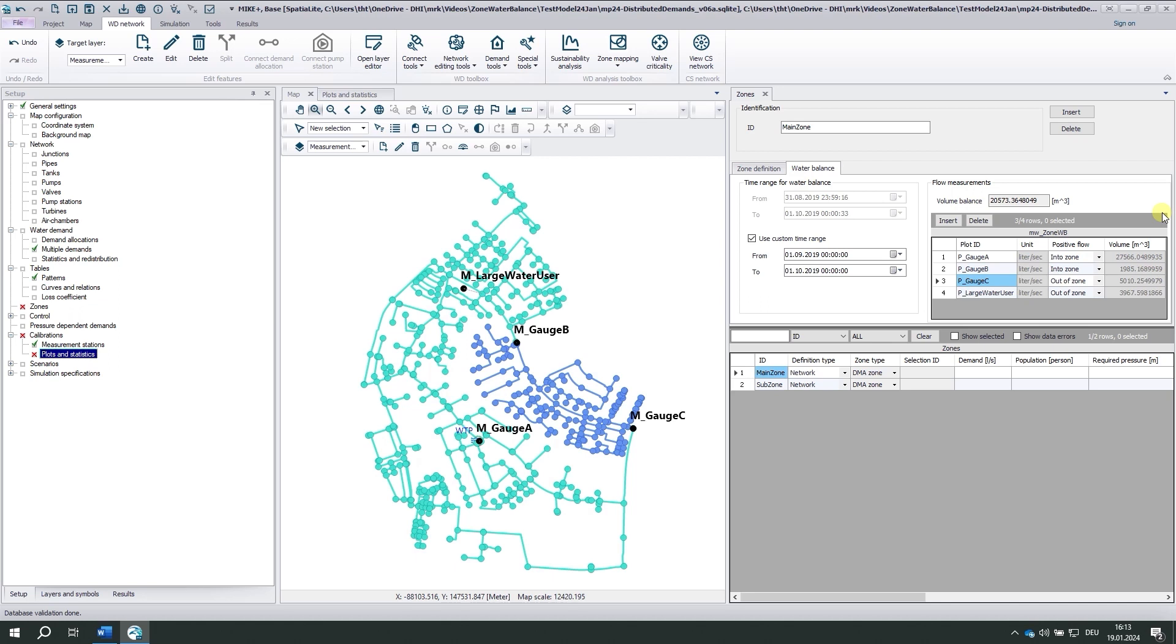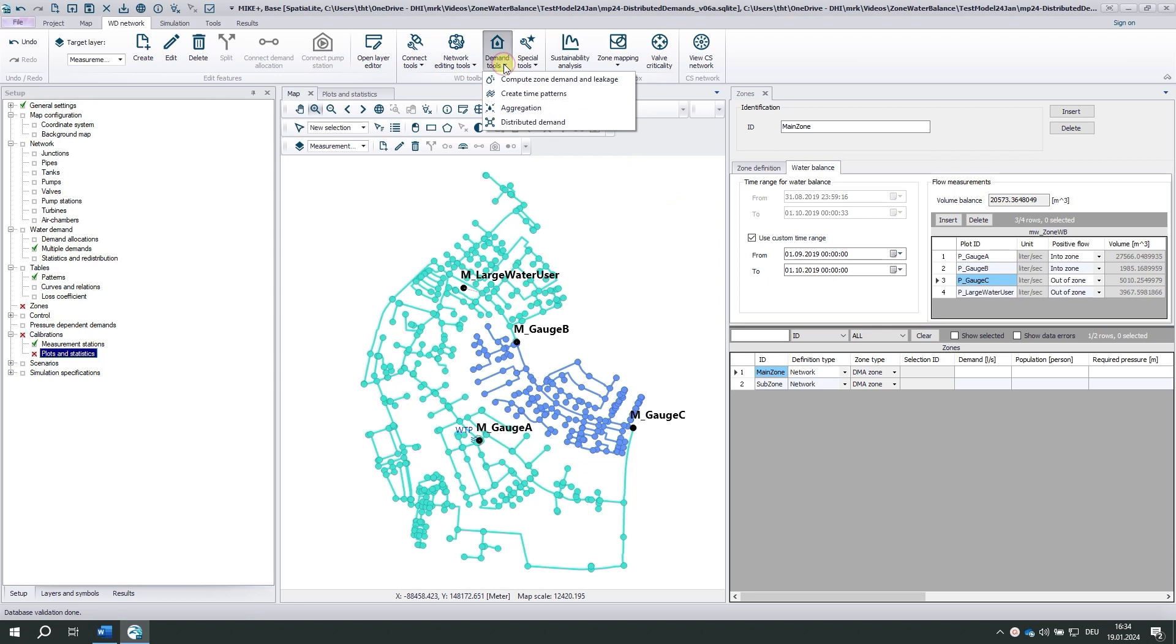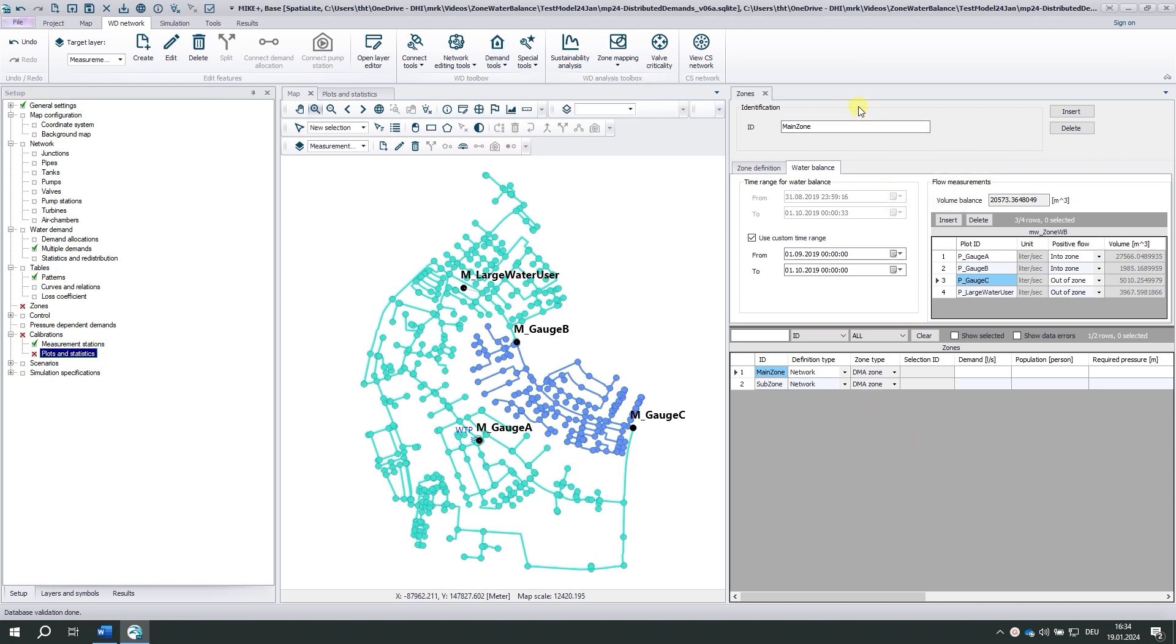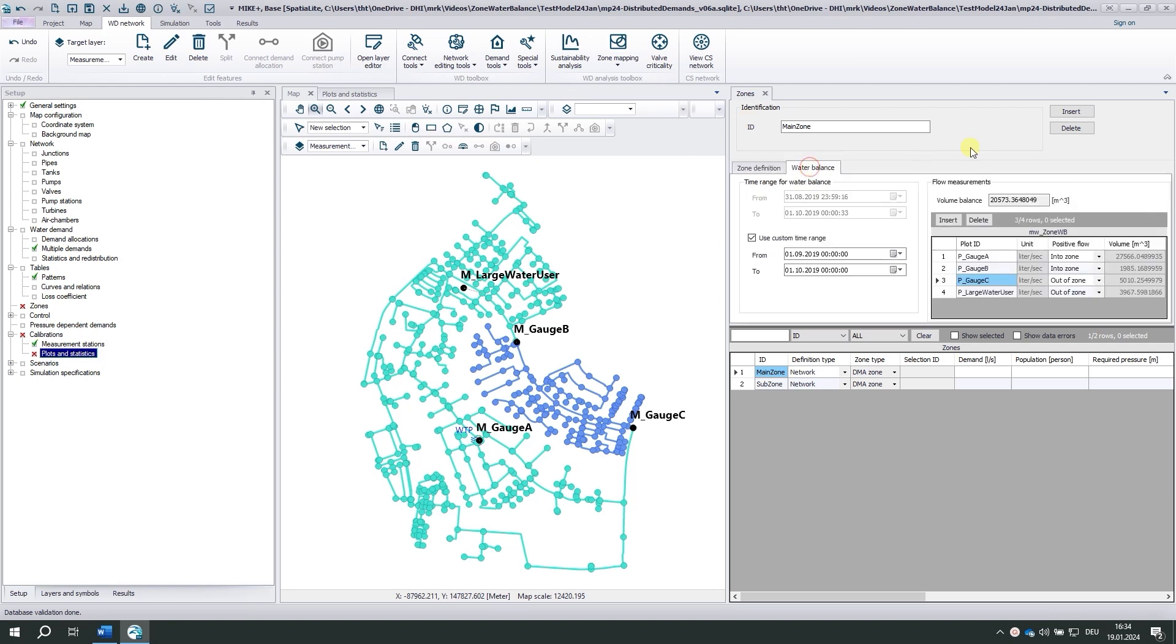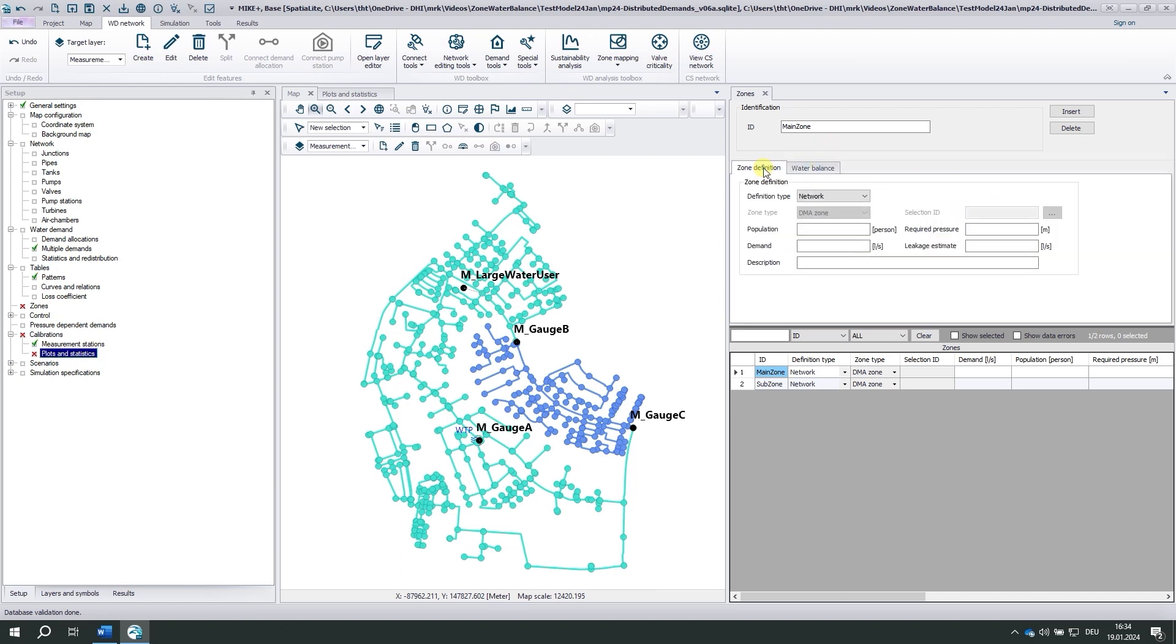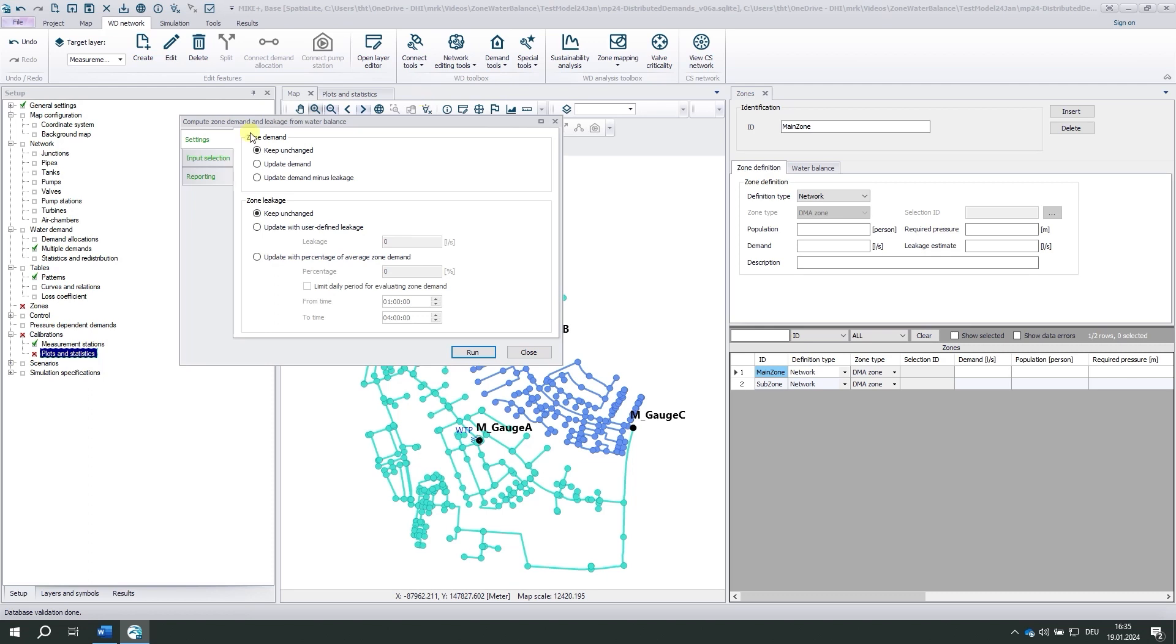Now that we have defined our two water balances, we can start with the really useful tools. They are located under the demand tools: Compute zone demand and create time patterns. What is the first tool about? You've probably noticed these two attributes here: Demand and leakage estimate. Compute zone demand takes the volume from the balance, converts the cubic meters into liters per second, and writes the results into the zone definition. Let's see.